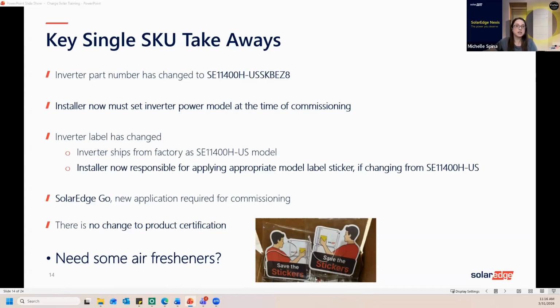To piggyback on your question and look at it another way, if you have installers that accidentally lock in the nameplate rating improperly—say they get on site, disregard the envelope with the stickers, and simply scan and commission it as an 11.4 because there's an 11.4 label on there, then realize it was supposed to be a 9.6—they can call into our support center and we can unlock that inverter. So there is a fail-safe if they need support to unlock it because they accidentally installed it improperly.